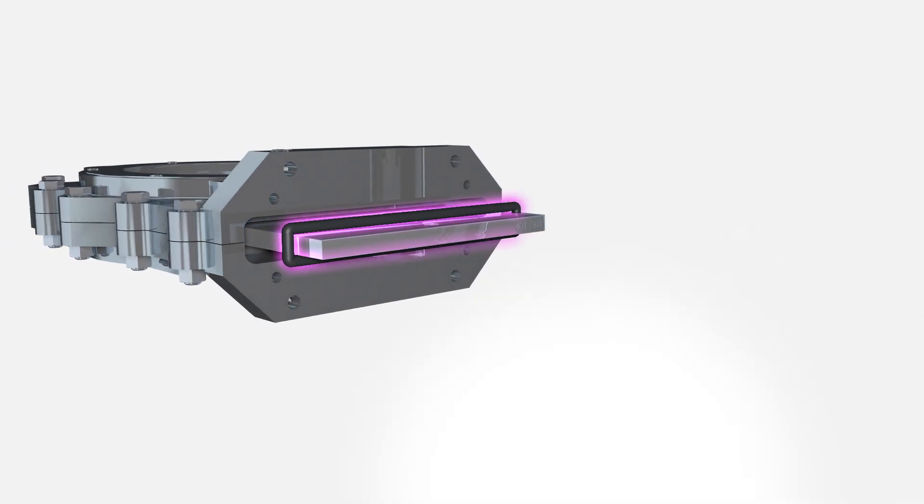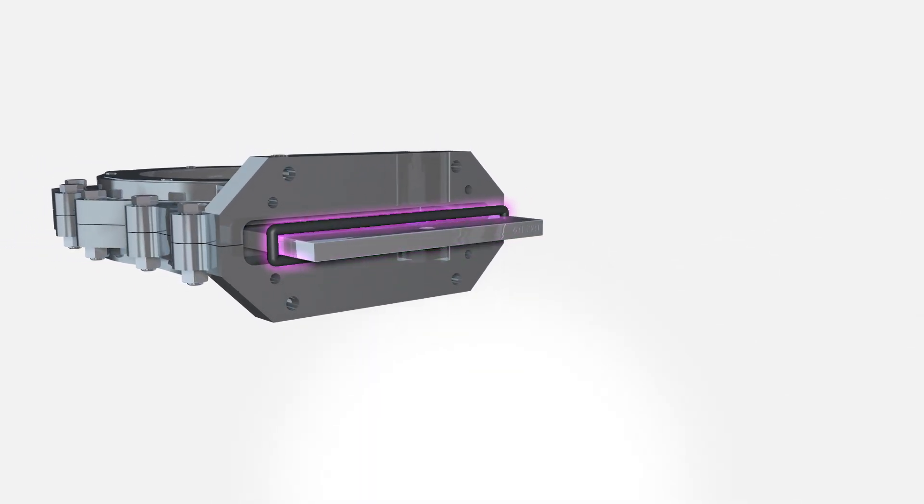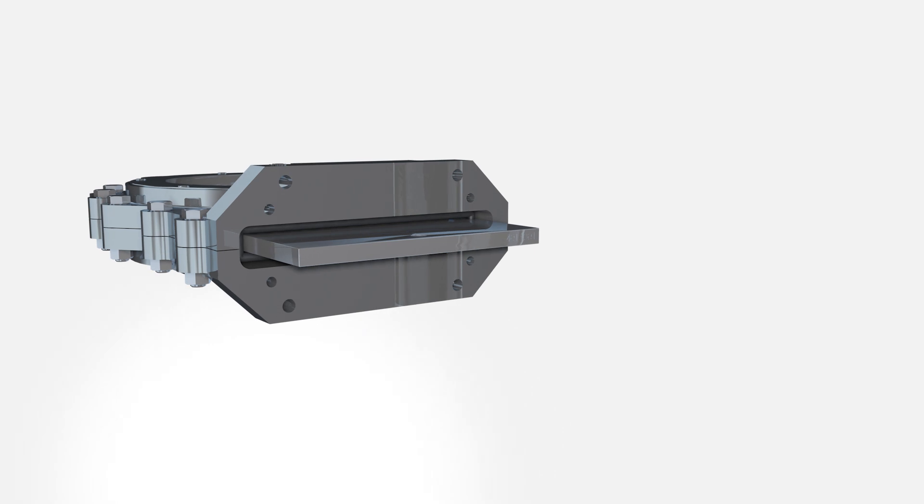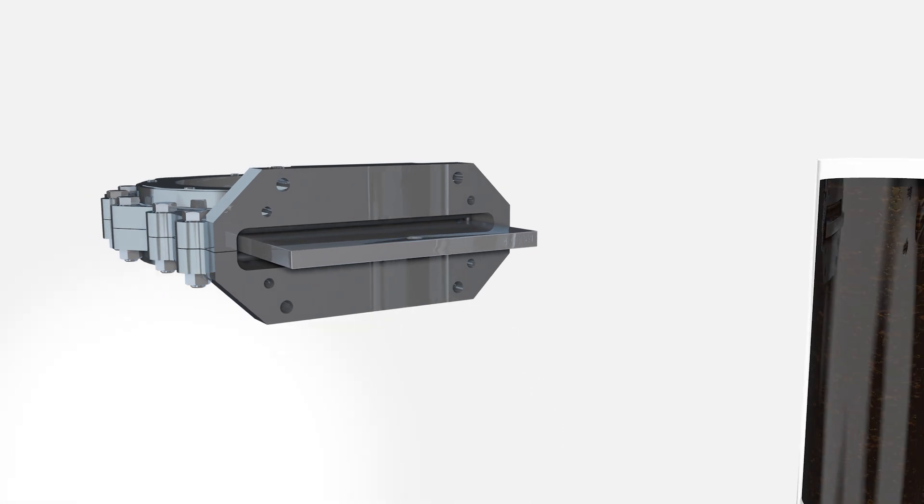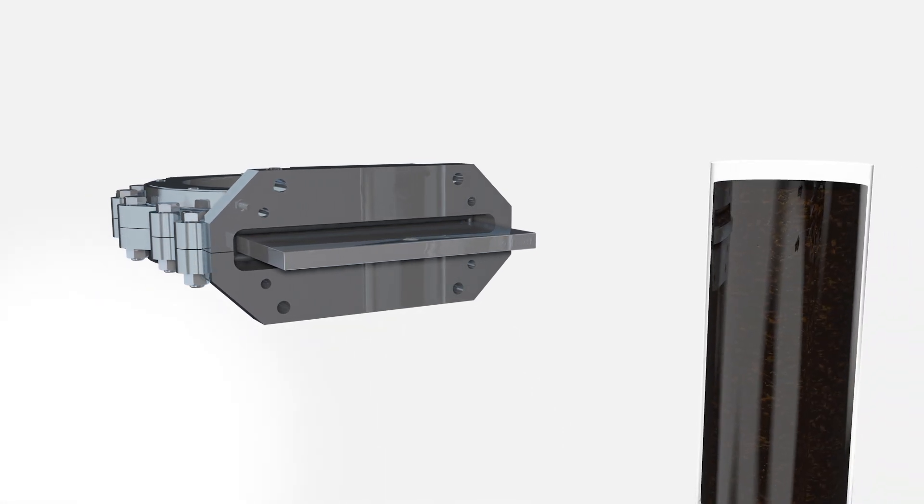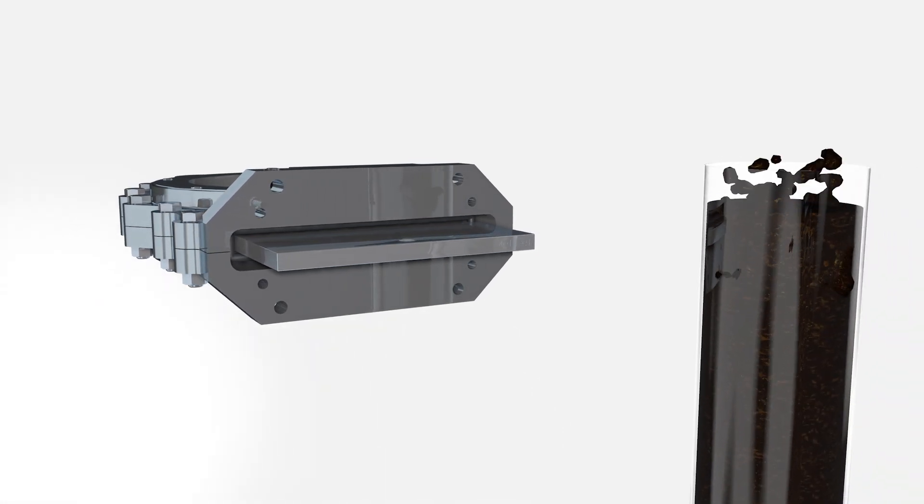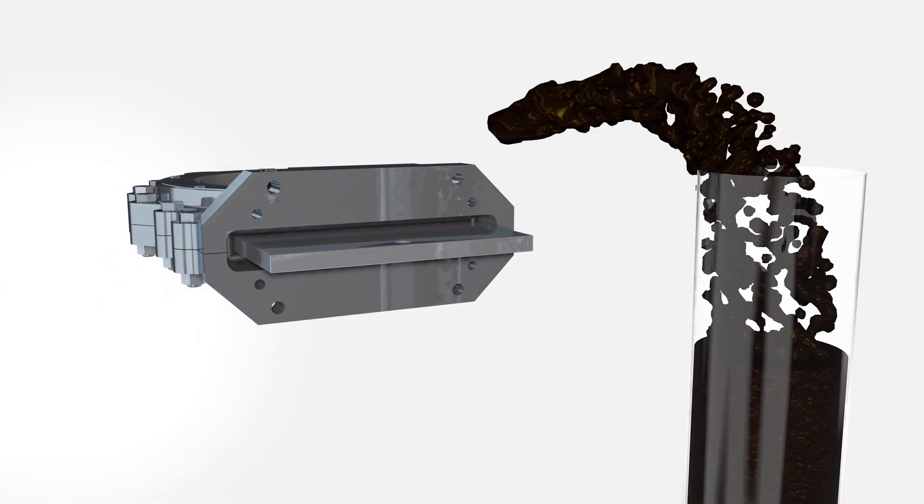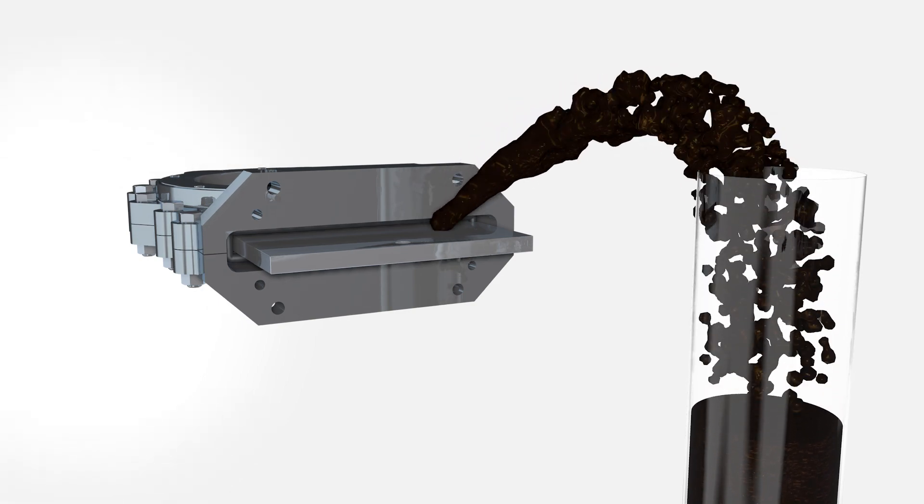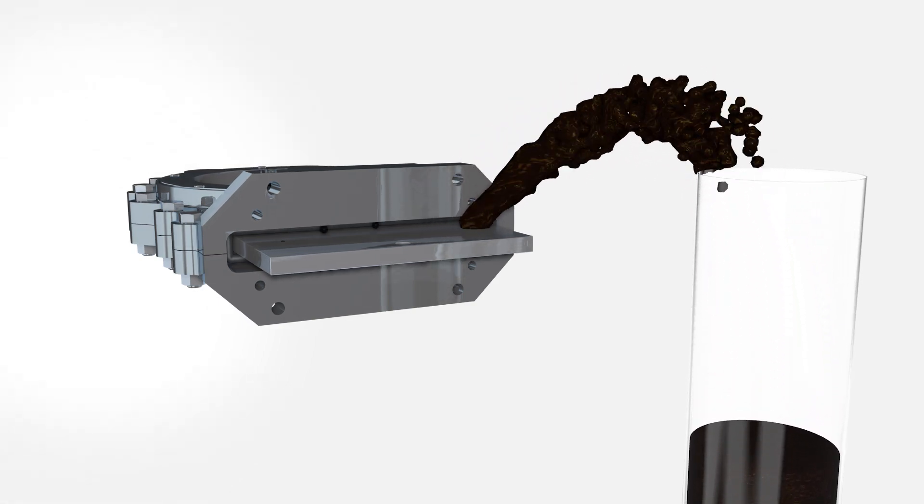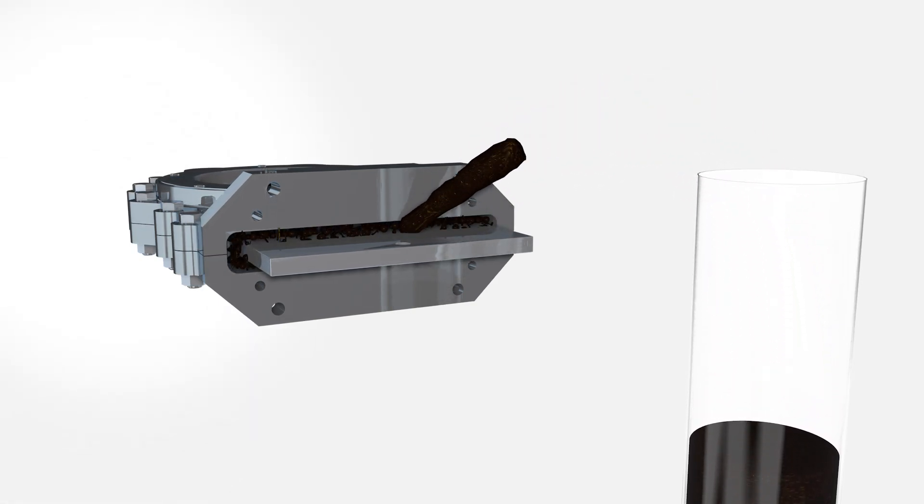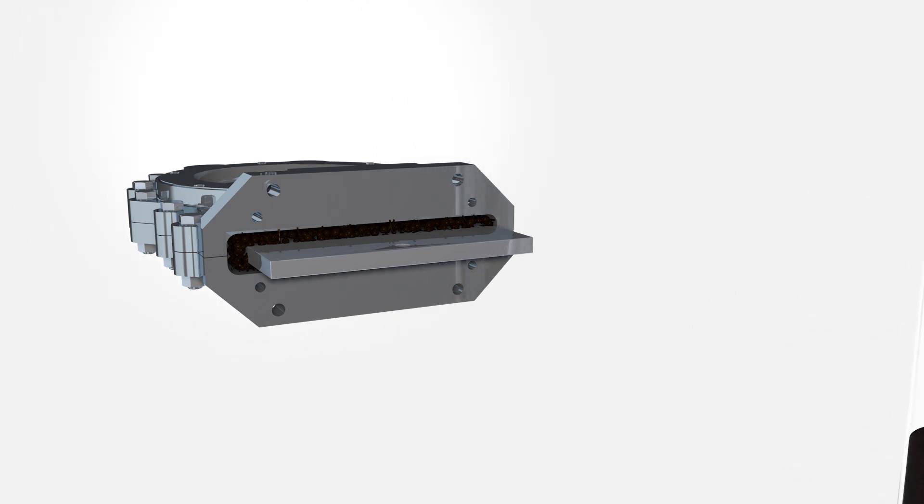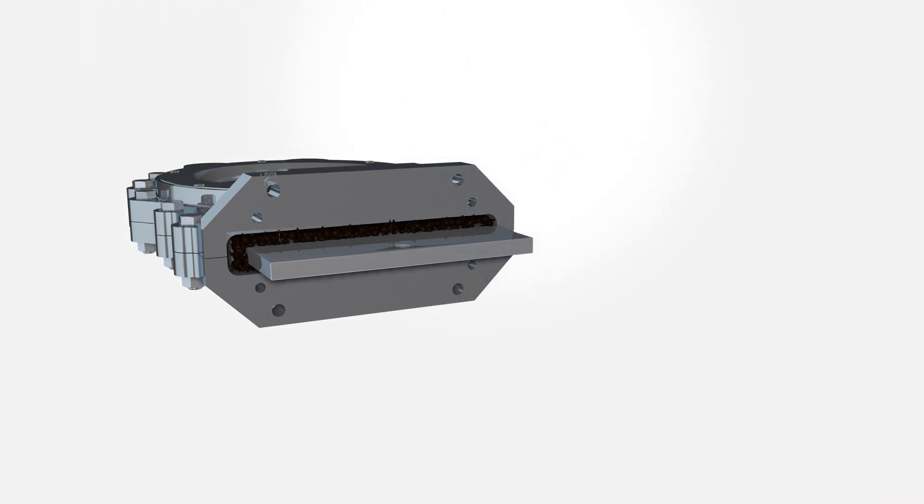Push the cord ring down evenly into the packing space as far as it will go. Next, evenly fill the gland space around the valve gate with the packing compound, tamping it into place as you go until the gland is almost filled. Leave approximately 3 mm of the gland unfilled.